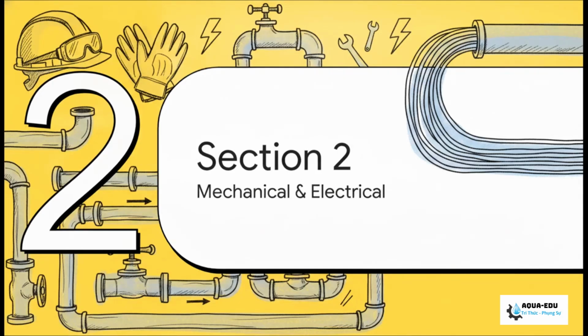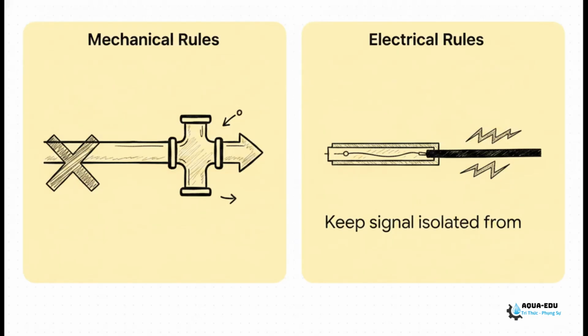Moving right along to Section 2, mechanical and electrical installation. You're basically wearing two different hats for this part of the job. On the mechanical side, it is crucial that you pick a representative piping location on your stainless steel line that has absolutely zero dead legs. We are looking for a continuous, highly stable flow. At the same time, on the electrical side, you've got to ensure your cable trays keep those delicate signal wires completely isolated. Keep them far, far away from noisy AC power lines and variable frequency drives. Otherwise, electromagnetic interference is going to be your worst nightmare.